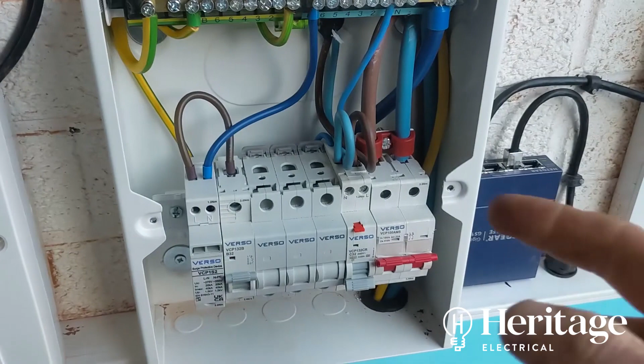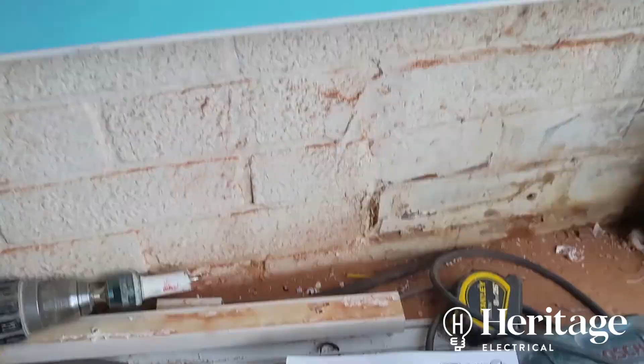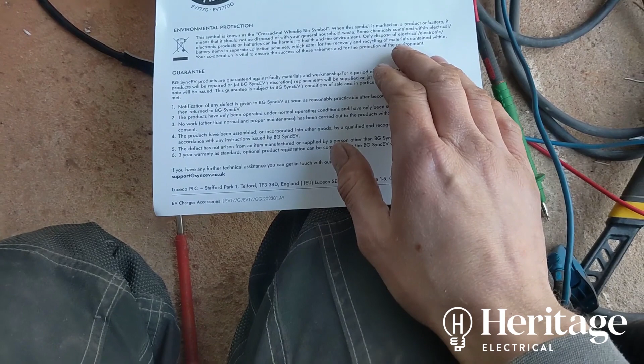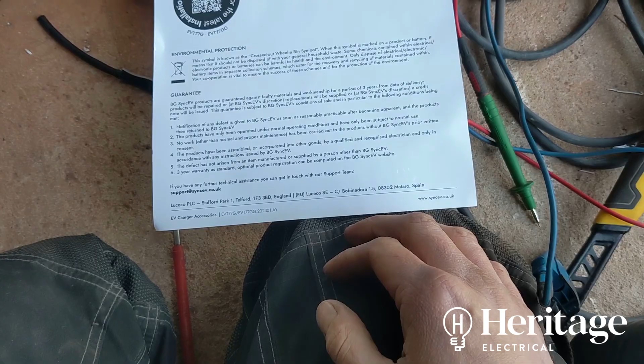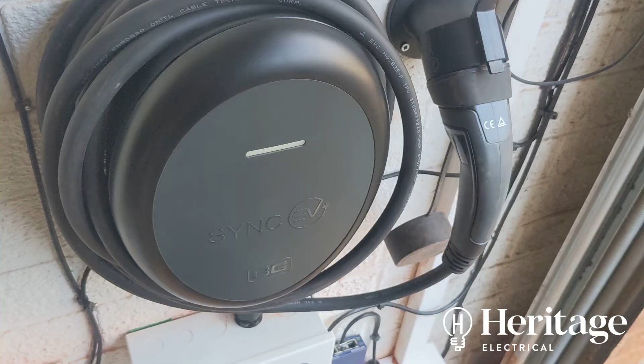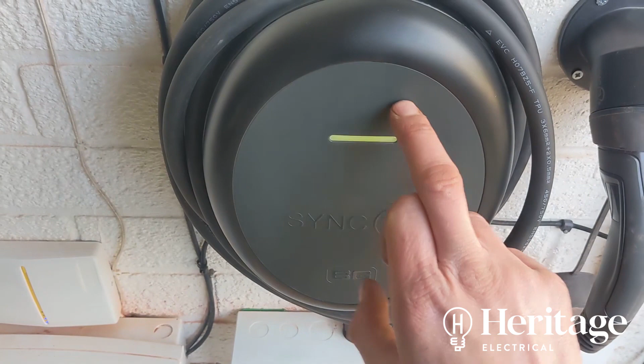Right, so we've just done our RCD test without the load connected, so I left the line out. So we've got our RCD test has passed, so we've done all our tests, and now we go through the commissioning process, and yeah, notification of the DNO. So this means that it's either waiting for network settings to be applied, or we've just applied some network settings, so in a moment this should turn blue, meaning that the charger's online and we can carry on with the commissioning process. Let's just give it a moment.